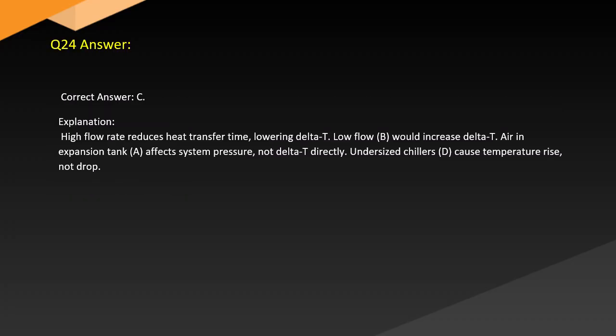Answer. Correct answer: C. Explanation. High flow rate reduces heat transfer time, lowering delta T. Low flow, B, would increase delta T. Air in the expansion tank, A, affects system pressure, not delta T directly. Undersized chillers, D, cause temperature rise, not drop.